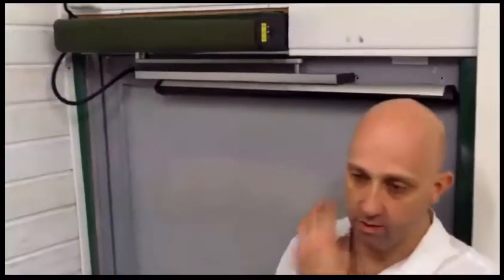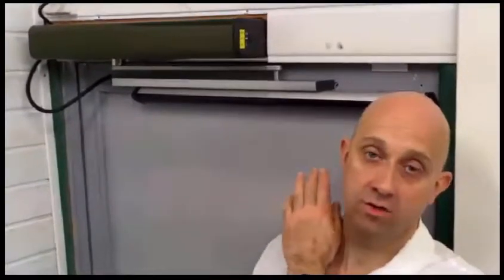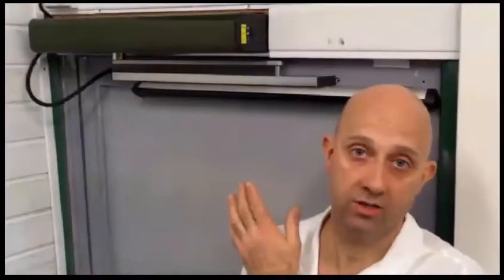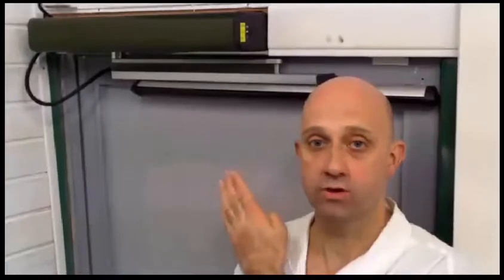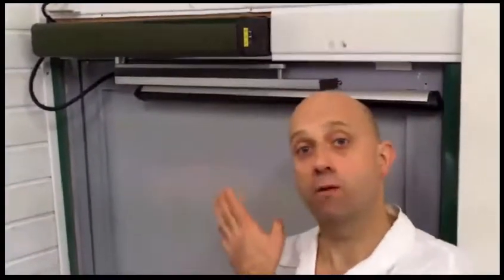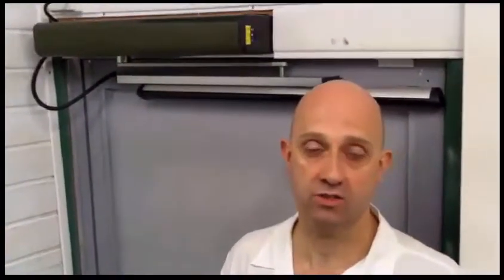The one really good thing that I like from a management point of view with the engineers is that there are no fuses on here. So you can't blow a fuse and you can't overload the system. We have what we call thermal fuses on there. So that if there's a short circuit or a fault or damage occurs with a sensor or an activation device somewhere, and there's a short circuit on that cable, you're not going to blow up the equipment. All we're going to have to get is a slight warming of a thermal fuse inside. Once the fault is isolated and found, then we can cure that, and then the thing will be reset and go back to working just as it was.